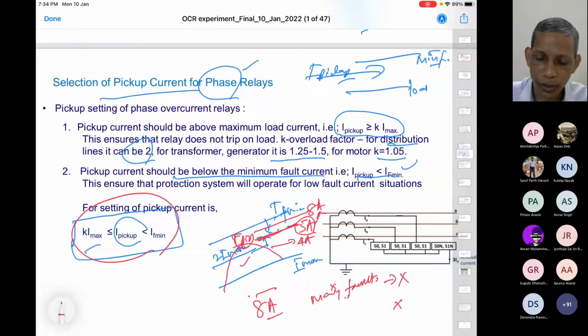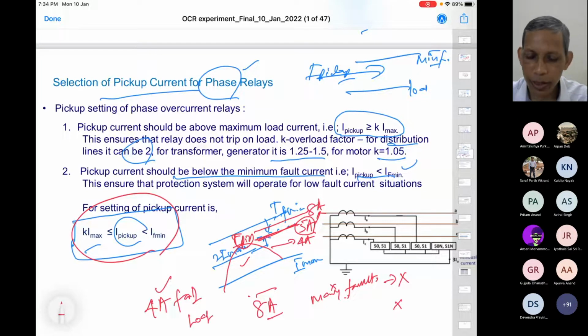So let us say we go for the 4 ampere. If you go for 4 ampere, all faults, including those with a fault resistance, will be identified. From the fault detection perspective, it is very good. But from the load perspective, any momentary load growth will trip it, which is not good. So between 8 amperes and 4 ampere with respect to 5 ampere, we see that in one case, from the fault detection perspective, this is good, this is not good. From the load perspective, this is not good, this is good.